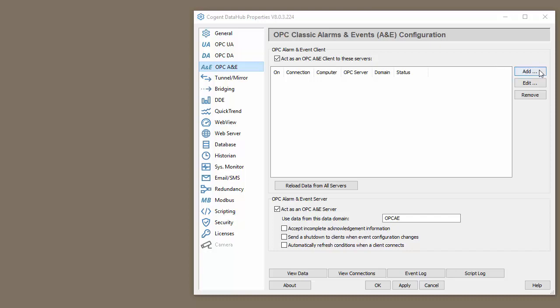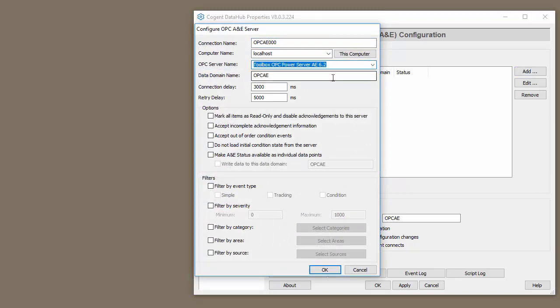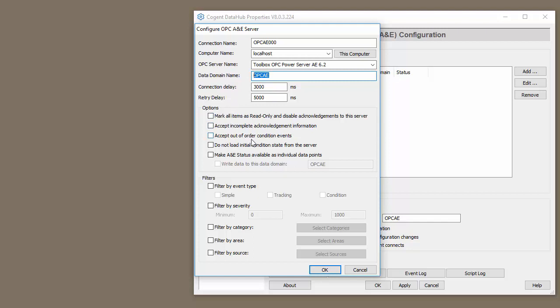The first step is to add a connection to our OPC A&E server. In this case, we're going to connect to our top server. We're going to put the data in the OPC A&E domain. Now this is only going to be the OPC A&E formatted data. If we want to convert the A&E points to individual DA or UA points, we need to check these boxes here and we need to specify what data domain we'd like to put them in.